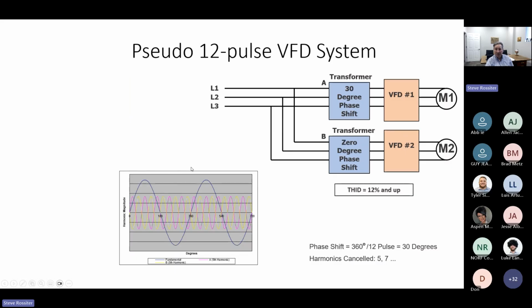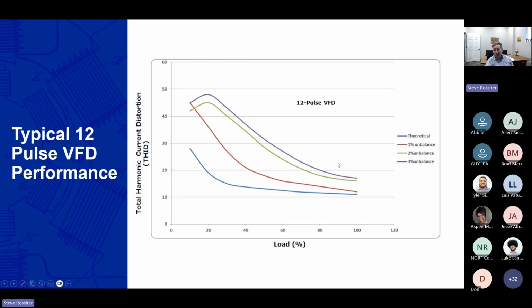Here's a simple 12-pulse pseudo system where you could take just two transformers and phase shift one of them. If those two drives and motors are equally loaded, you're going to reduce the harmonics substantially right off the bat, maybe 12% harmonics with that technology. And there are also other ways of having a phase shifting transformer. Well, when you get to an 18-pulse, that might be more clearly defined. The challenge with that is when you have voltage imbalance, and with load reduction, you do have some loss of mitigation of harmonics.